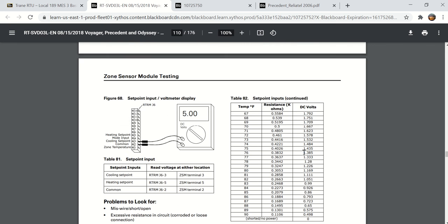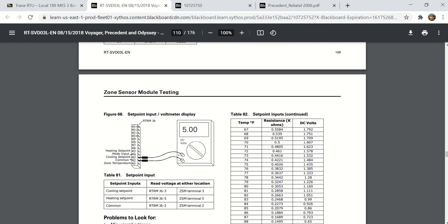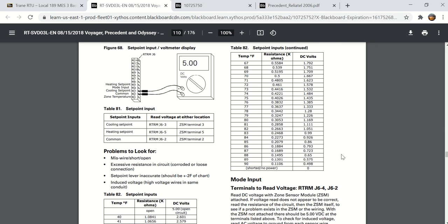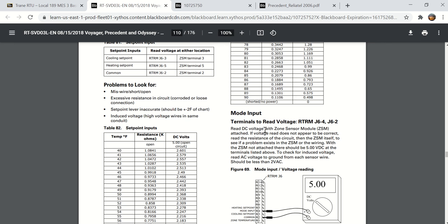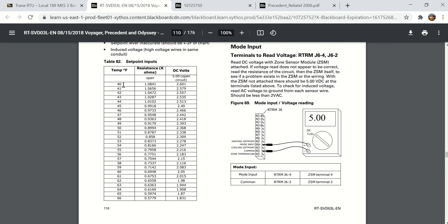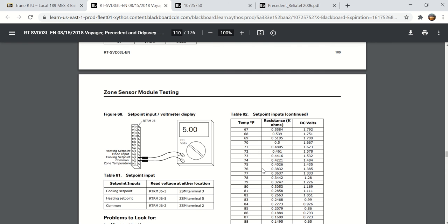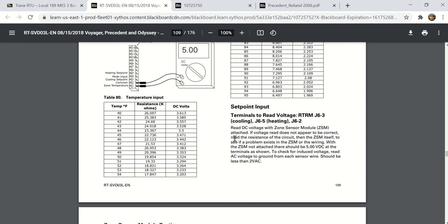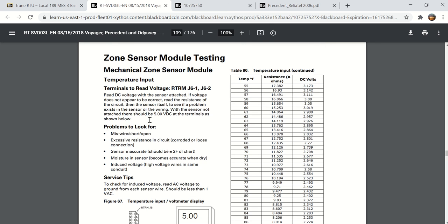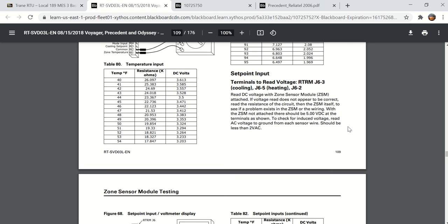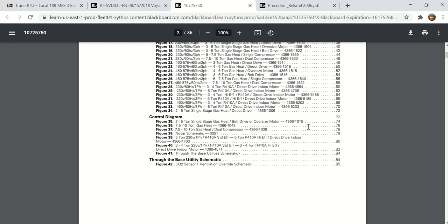is. And then if you scroll down, now you can tell on cooling set point. So you want to know what the slider or the potentiometer, the dial for cooling set point is set to. You read the voltage between 2 and 3, and you look at this scale here. It goes from 40 degrees to 66 degrees, and then this table here, 67 up to 90 degrees. So if the cooling set point was 72 degrees, it would be 1.578 volts you would read there. So a lot of information in this Reliatel manual, and a lot of the information that you'll find in there is going to be information that's going to be asked on the quiz.